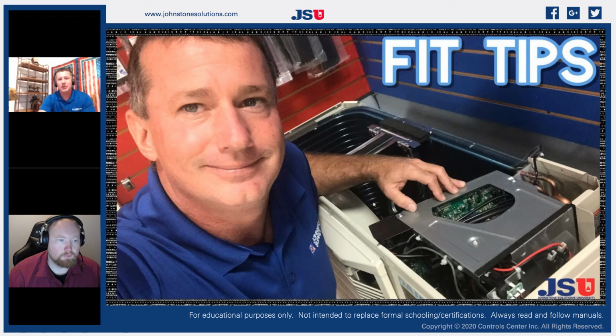So as we continue talking about inverter technology, and particularly inverter diagnostics and troubleshooting, that's where we're at right now. Last week we talked about using the diagnostic tools that are going to be available for these new pieces of equipment, using error code retrieving that is in the thermostats, these intelligent communicating thermostats, using the individual components to be able to focus in on what those error codes are, to be able to see a little bit more detail than maybe what is only at the thermostat.